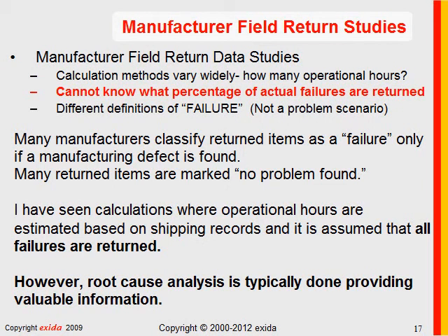What about manufacturers' data studies? When I worked for a manufacturer, I was taught to calculate operational hours based on shipping records. And we assumed, of course, that we shipped the product and it was hooked up and connected within a week. We also assumed, of course, all failures are returned, because why wouldn't somebody return it to us? Well, the answer is it costs money as the first reason, and people are busy, and there's dozens of other reasons. The bottom line is manufacturers have no idea how many of the actual failures are being returned.